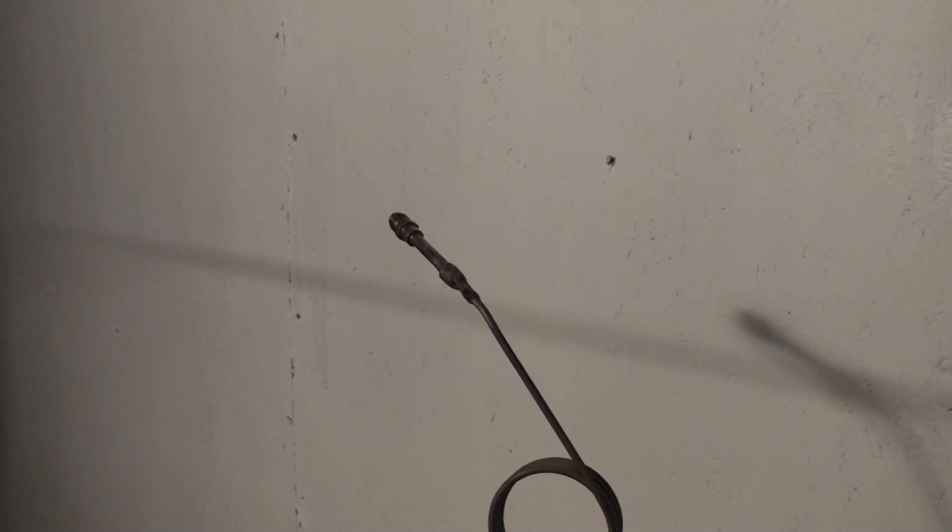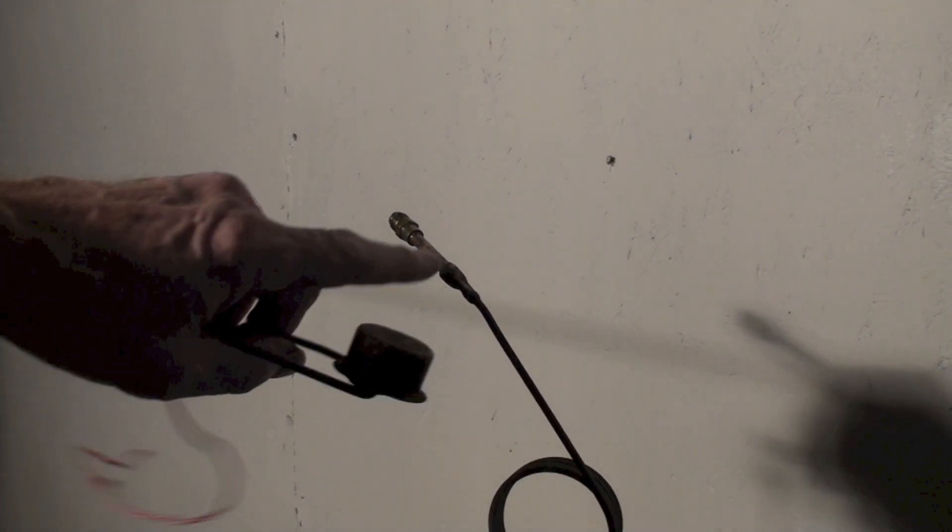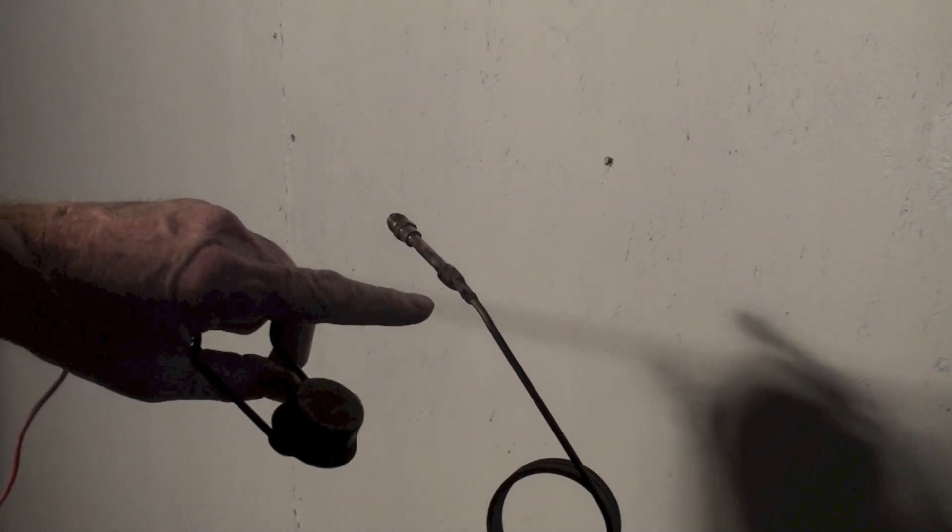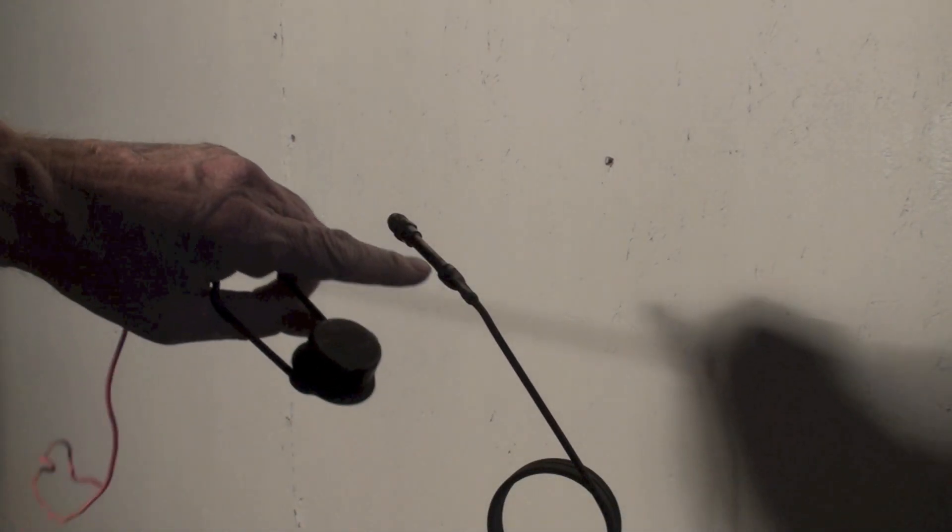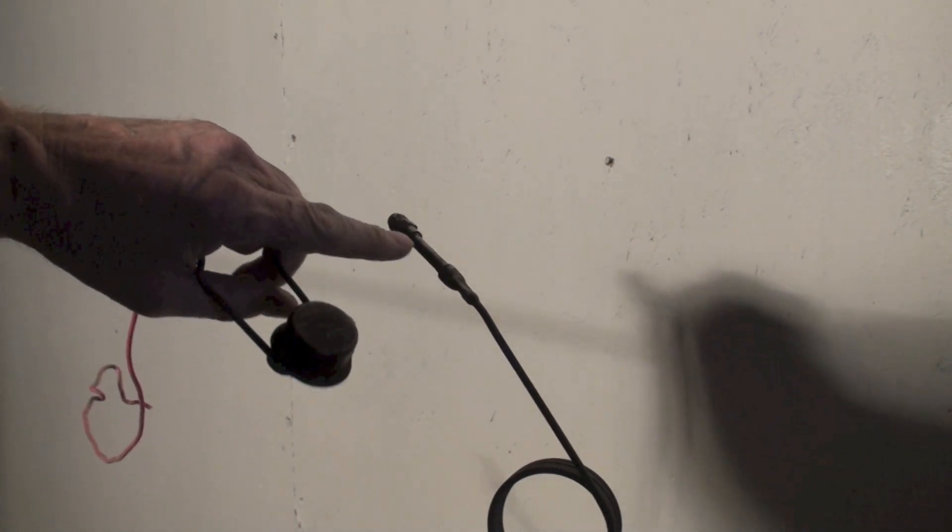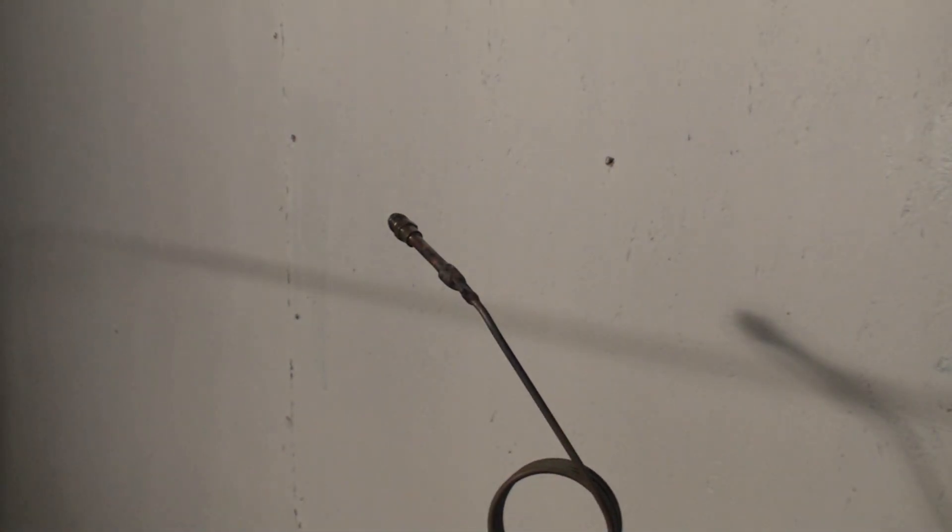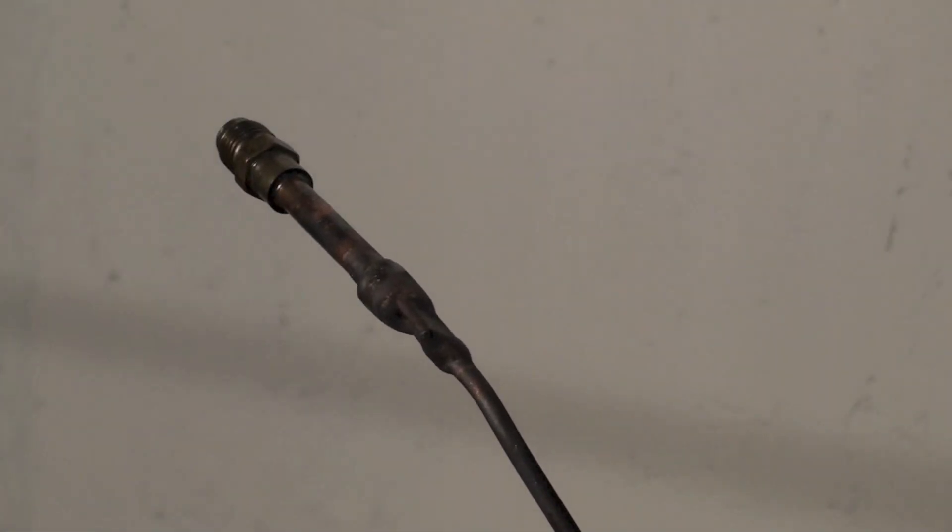Okay, as I'm pulling the taps off of this outdoor coil that I tested for leaks and did some repairs on, there's one thing I wanted to show you. I'm going to be pulling this off - it's where the cap tube normally goes into a 3/8 tube right here. Let's get a little closer there.